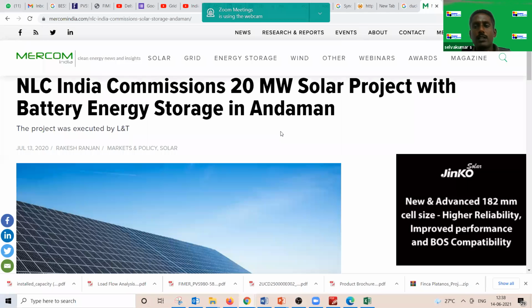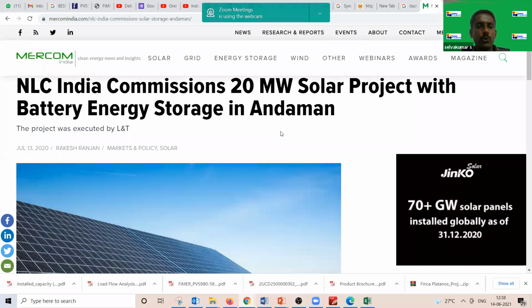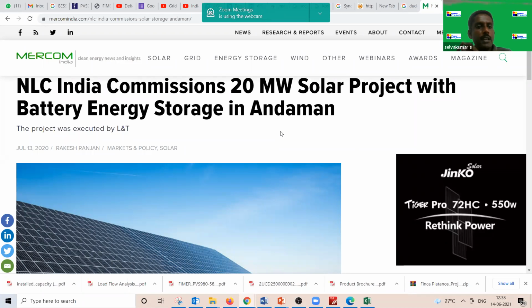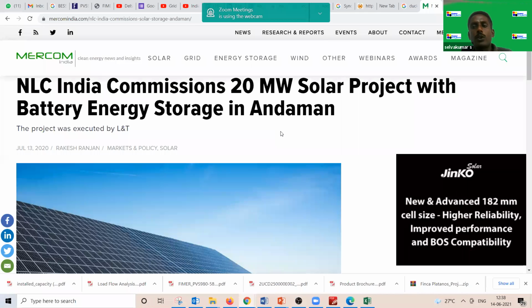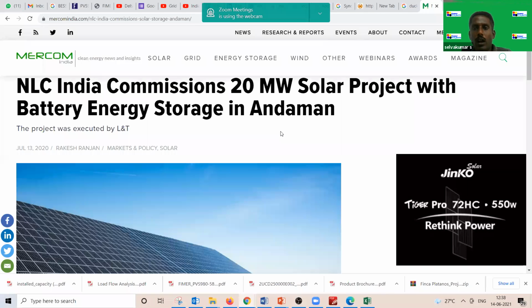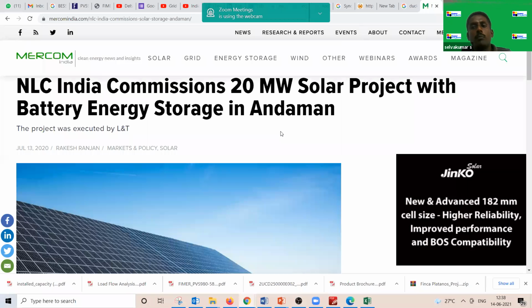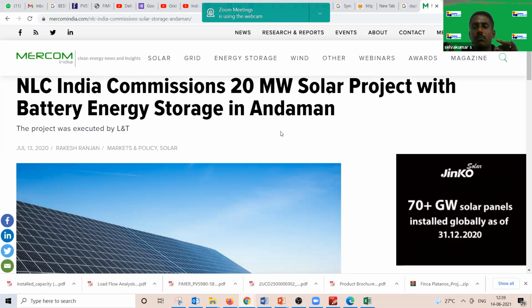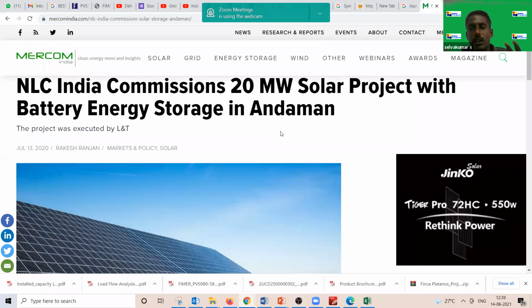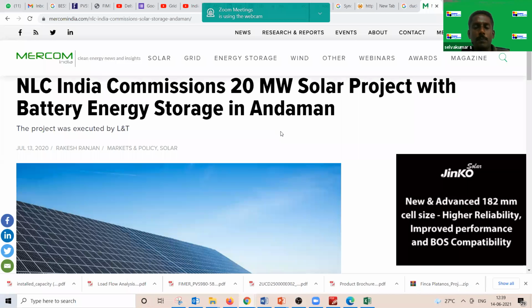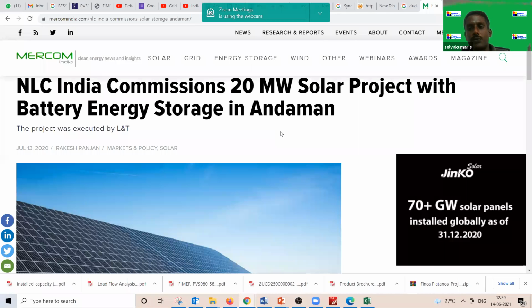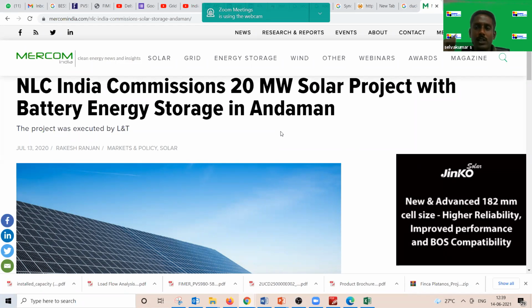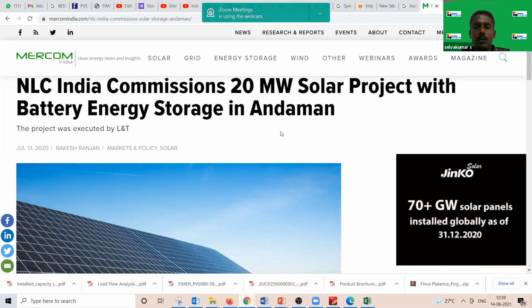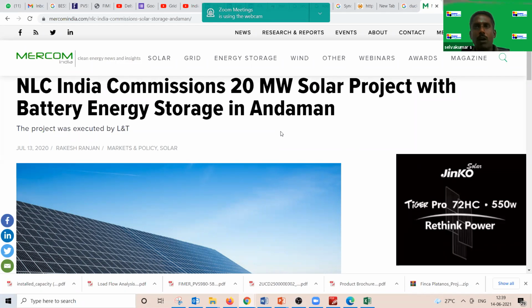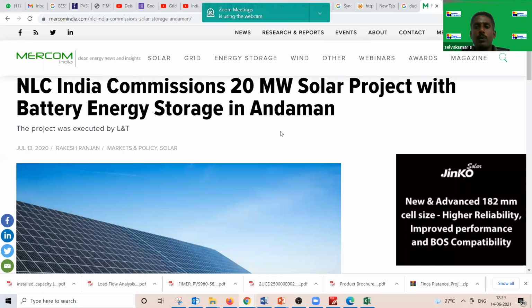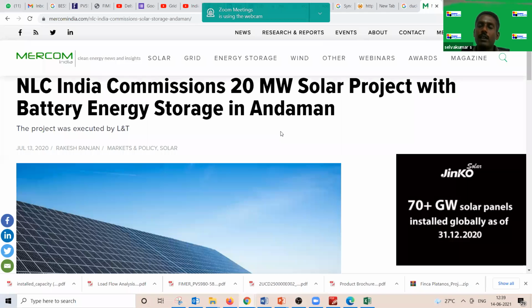This is a typical example of energy shifting applications. Andaman, as you probably know, is a tourist spot, at least before COVID, and the peak demand in the evening is exponentially high from 6 to 10 p.m. They don't have other sources and predominantly run on diesel generators. The average levelized cost of energy generation in Andaman Island is about 29 rupees 50 paise per unit. If you're in Tamil Nadu you enjoy the first 100 units free, but Andaman spends 29 rupees 50 paise to generate one unit, one kilowatt hour, because they depend predominantly on diesel, which is costly to transport to an island, and also because their load curve isn't flat—it's extremely high in the evening.